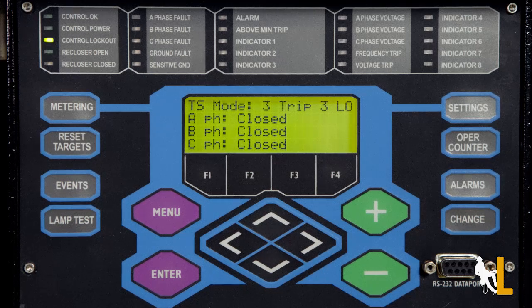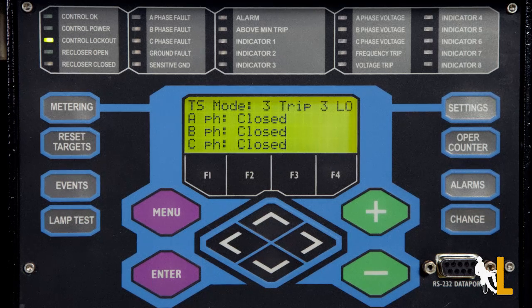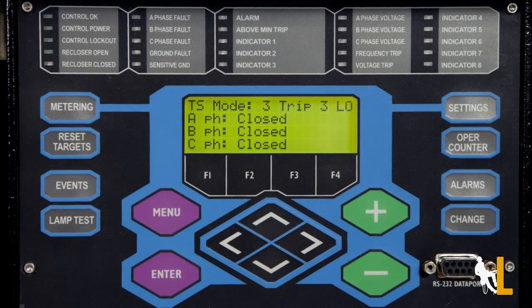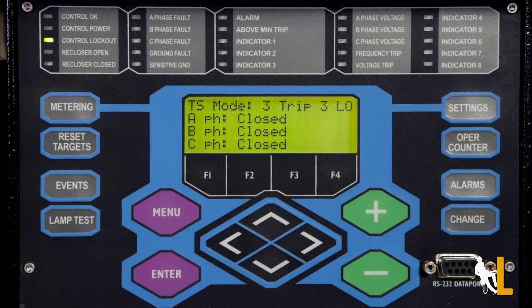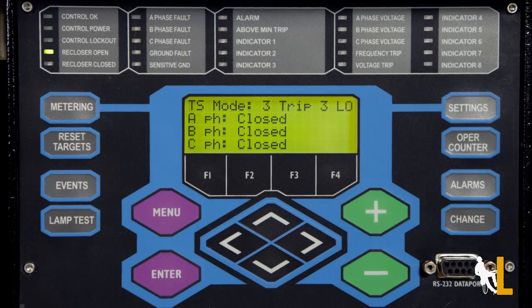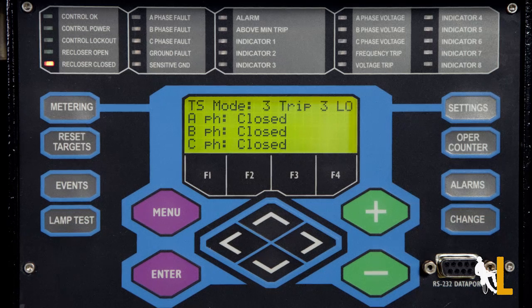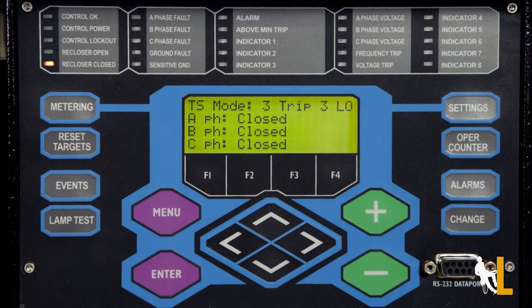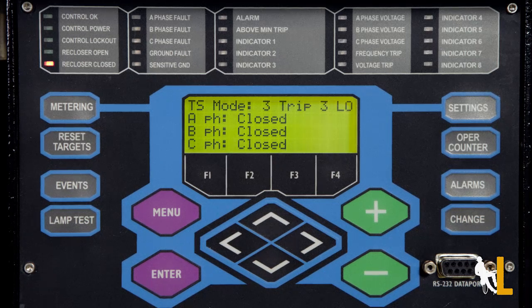If the control lockout is steady green, the control for all three phases is locked out. And if it is blinking, only one or two of them are locked out. Same with the recloser open and closed. A steady light indicates that all phases are open or closed, and a blinking light means only one or two of them are.